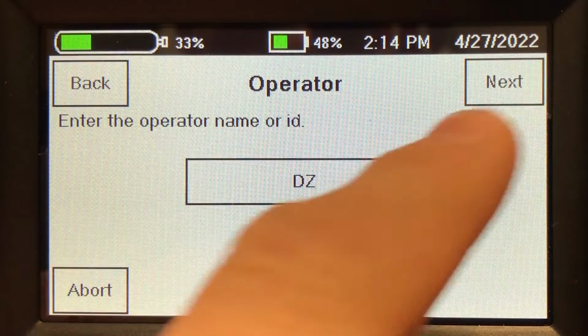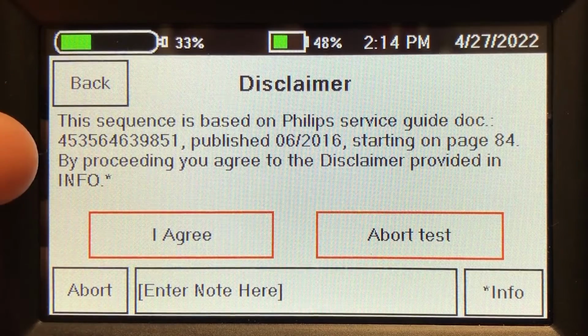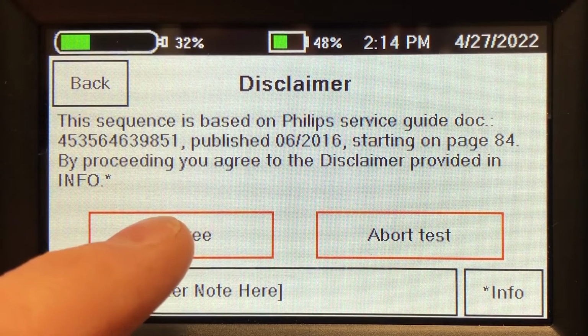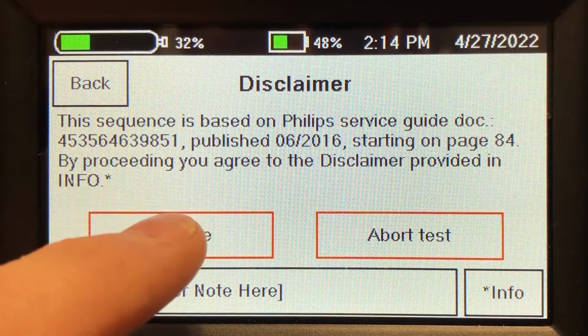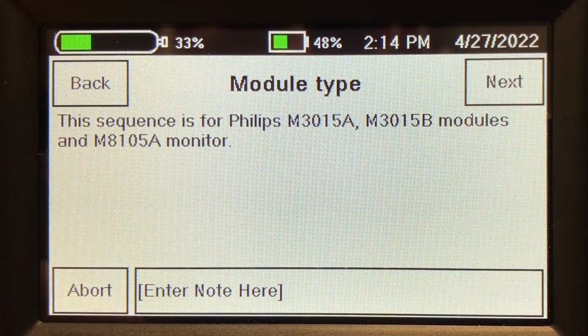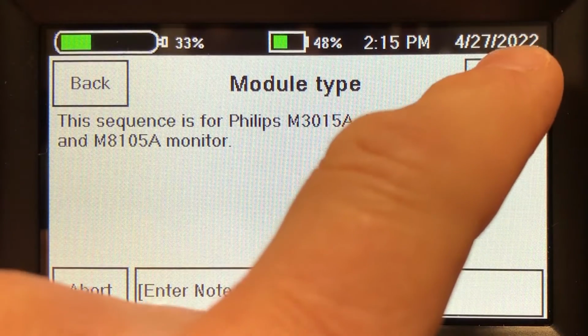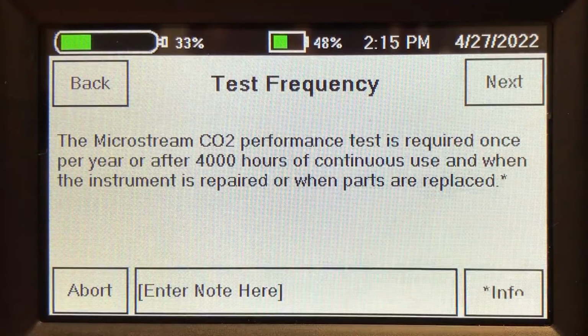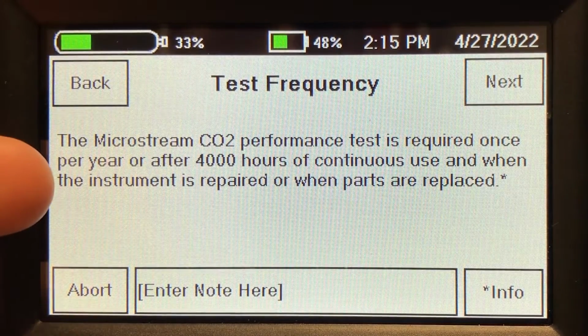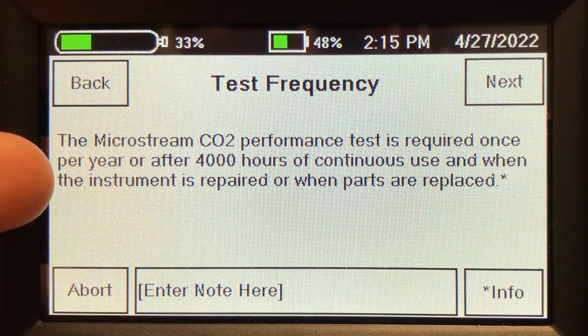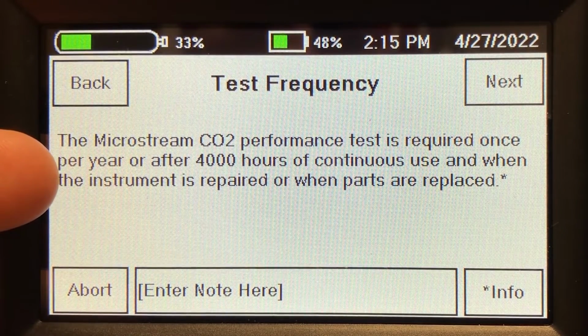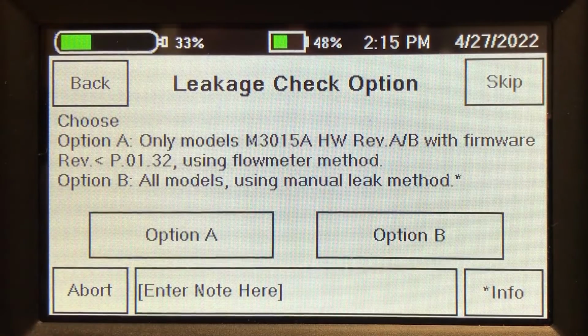Enter asset ID, operator initials. This tells us what service manual it comes out of. We agree that it's our responsibility to figure out exactly what sequence we should use for the device we're testing. This tells us which module types this applies to. This tells us that we should do this test every 4,000 hours, or if we've replaced parts, or once a year. So now we've got to pick.